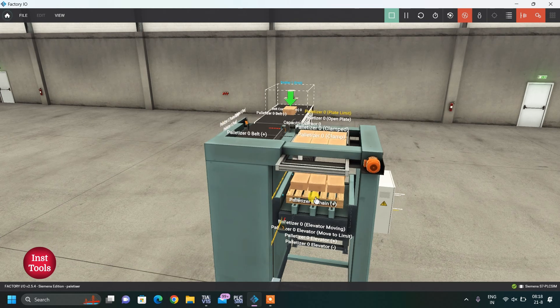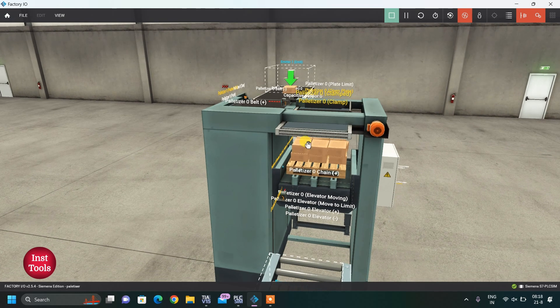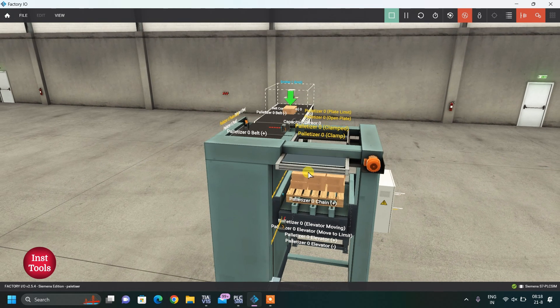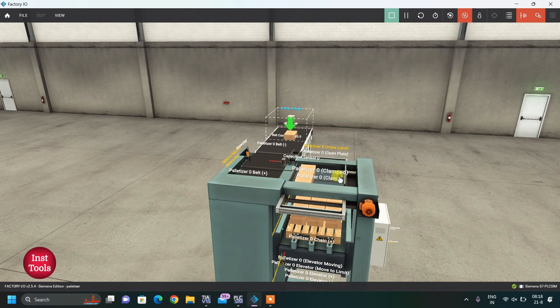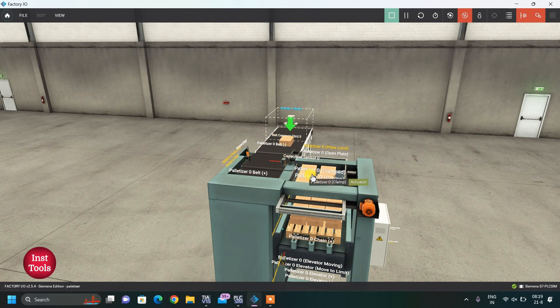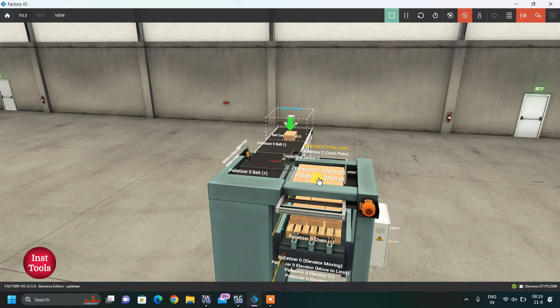While all the boxes are stacking here, the elevator should remain in position. The logic is: two boxes pass through this sensor, pusher is activated and moves one time — it should move three times total. Again two boxes come, pusher is activated a second time. When the pusher moves for the third time, it will clamp the boxes — you can see the clamp — and the door will open.